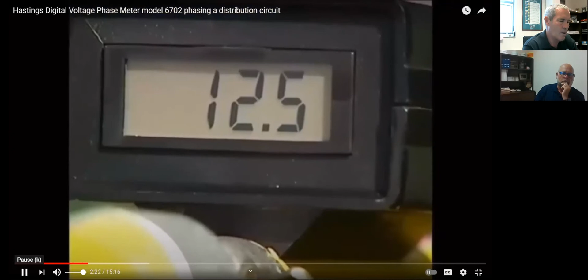Check it across. All right, see guys, what they were doing there, to give you a better understanding of what Professor Shoemaker said: when they were hanging these hooks on this side, they were checking this side of the pole. Going bottom side switch to bottom side switch, they're checking voltage on this side. This jumper comes around to the bottom of the switch. It's a good idea as far as safety goes, because you're not having to reach through these phases to the other side to check it. They can get it from bottom of switch to bottom of switch. A little easier for them.